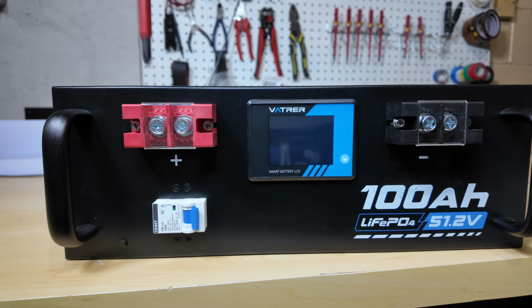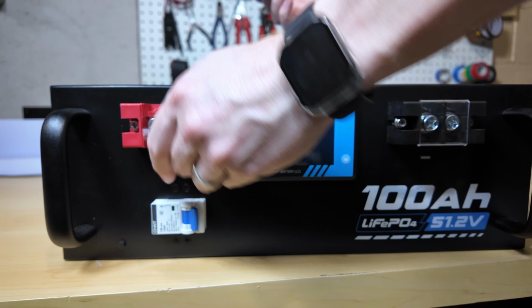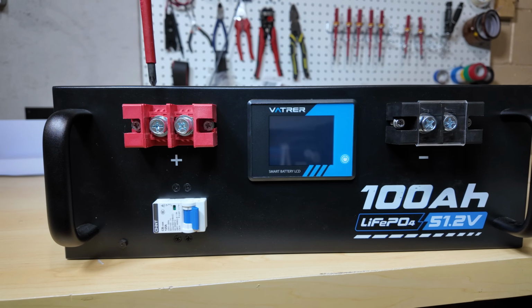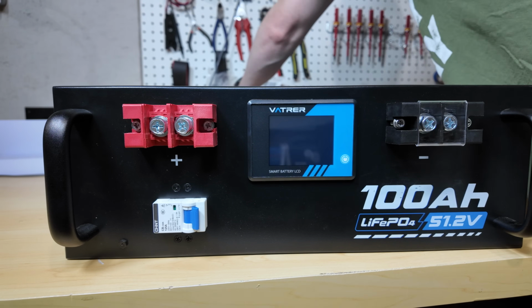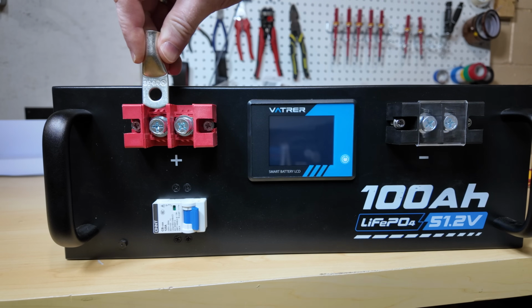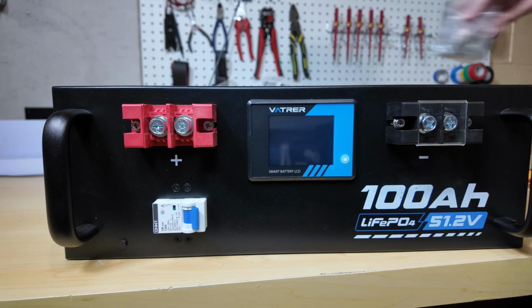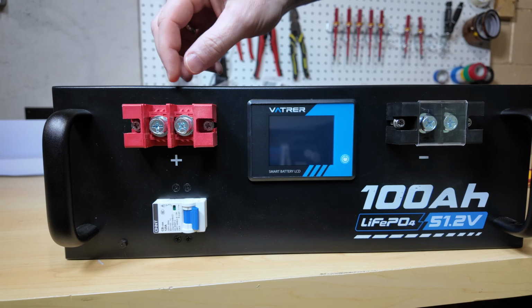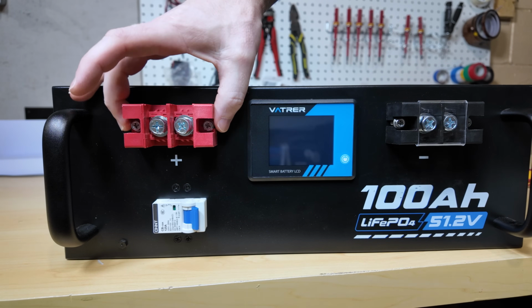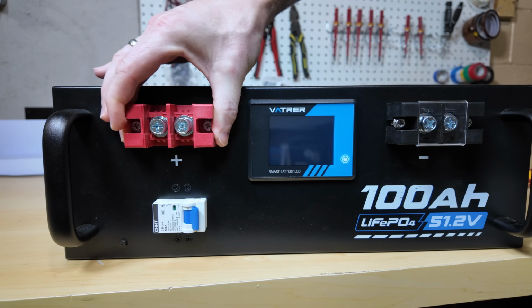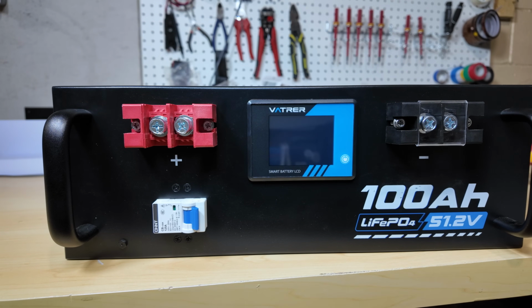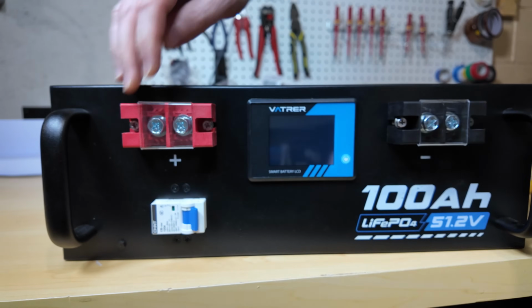A couple things to note: I am not a fan of these style battery terminals. Other people might like them, but I don't, for two reasons. One, this is very tight spacing in here—trying to get a larger lug in, you might get a 4 gauge in there, but you cannot get a 2-aught cable in there, maybe a 2 gauge cable, maybe, and then it might be spreading out. The other reason is you only have 2 bolts on the side holding this in, and they usually end up wiggling themselves free over time when you're trying to tighten things down. But they do have 2 terminals, so you can put 2 smaller gauge cables on here. I believe these have M8 bolts with a washer and lock washer on the end. They do have covers to go over the terminals to keep fingers off, which is nice.